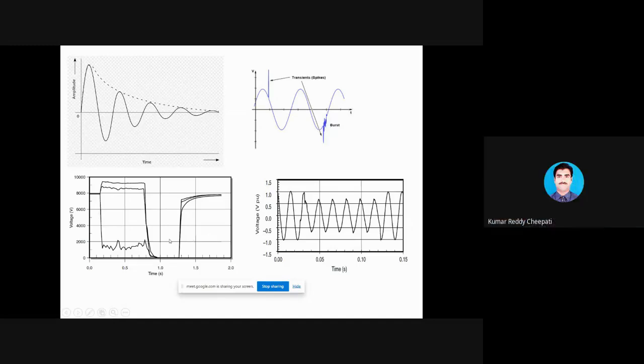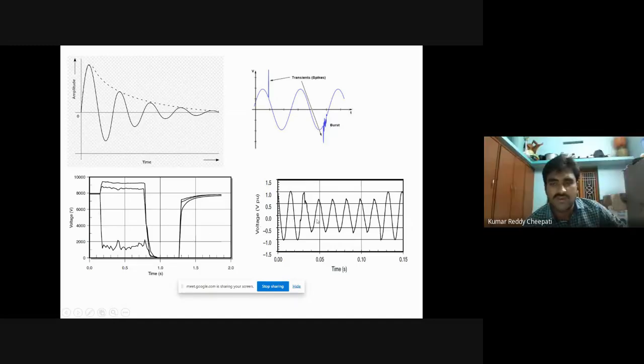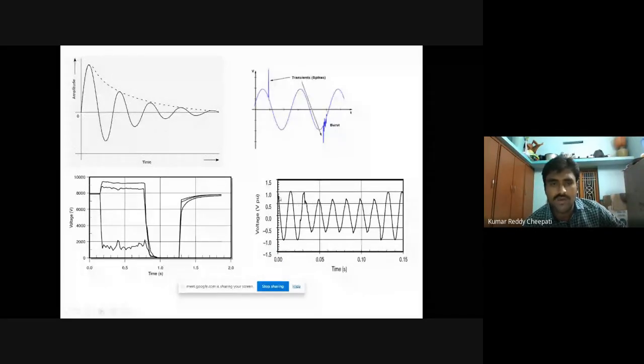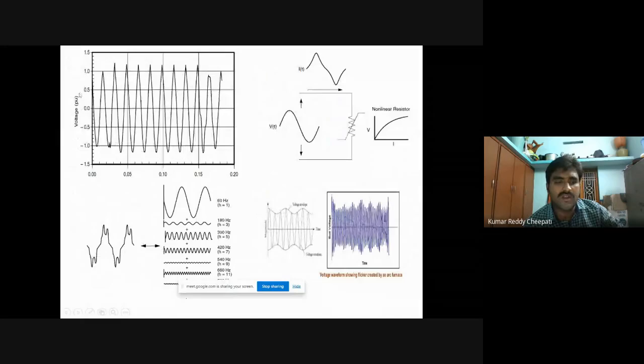And this is the indication of voltage sag, where the amplitude is reduced to less than 1 per unit for a duration of less than 1 minute. And this is the waveform showing the voltage sag. And this is the indication of voltage swell, where the amplitude is more than 1 per unit for a duration less than 1 minute. And this is the circuit diagram of a nonlinear load.